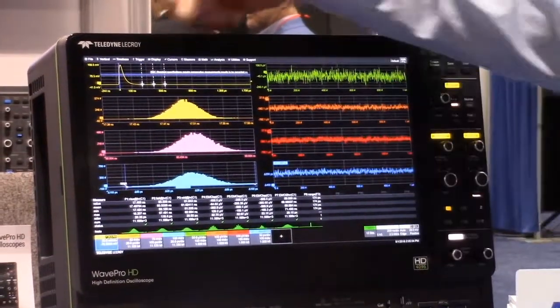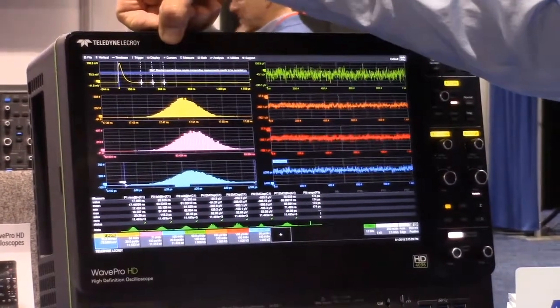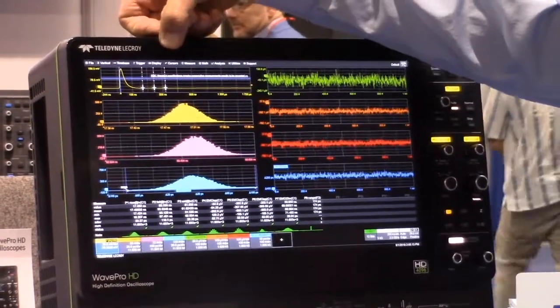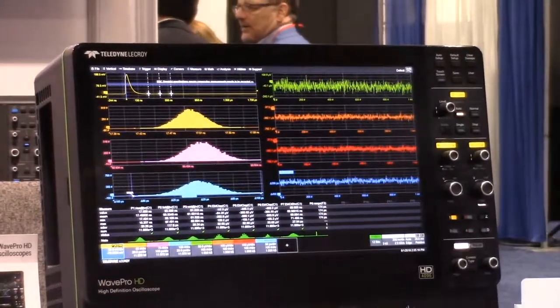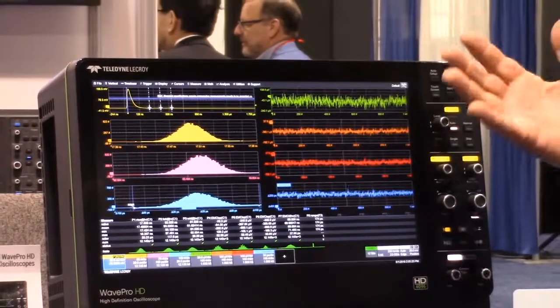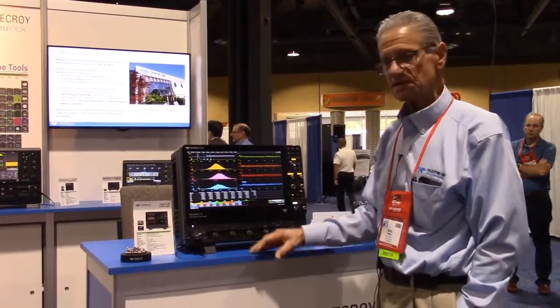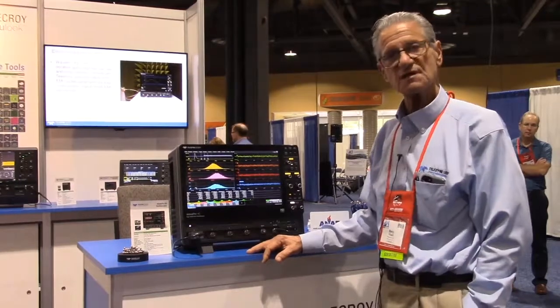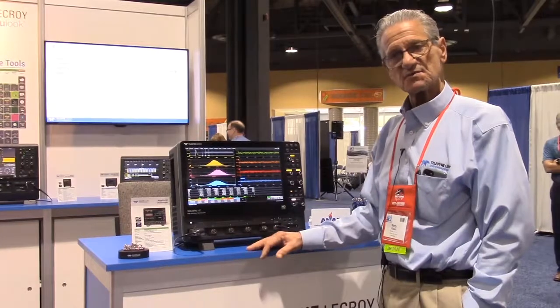We've also got three amplitude measurements after the ESD pulse decay, which is also specified by the EMC standard on how to make these measurements. We are displaying these measurements with statistics and histograms. As an add-on, I am trending four measurements, including the ESD pulse half-life measurement and the three voltage measurements after the pulse decay.